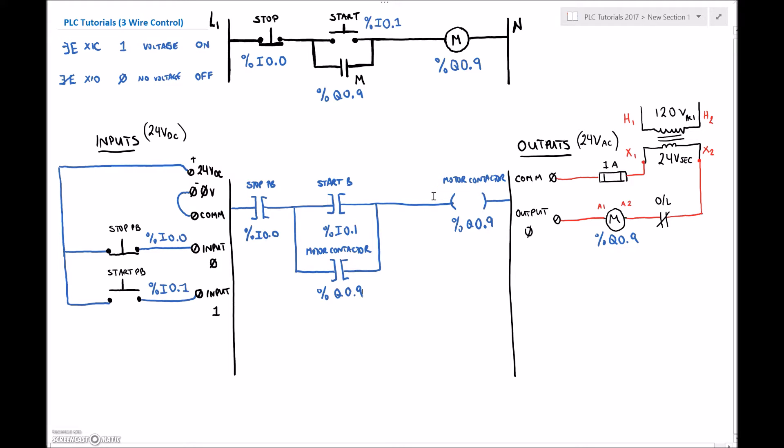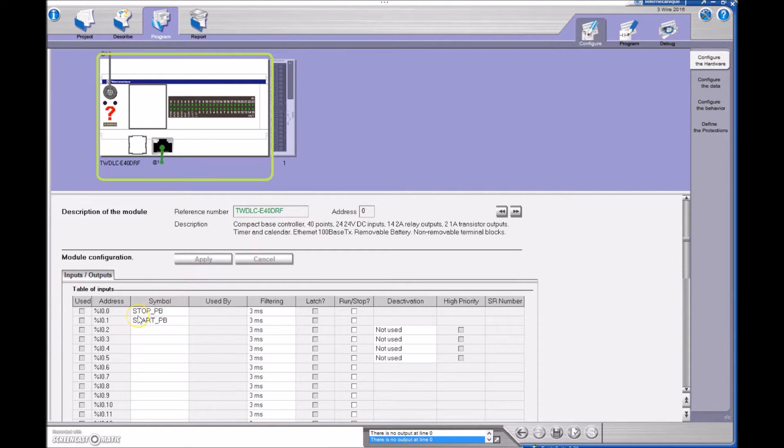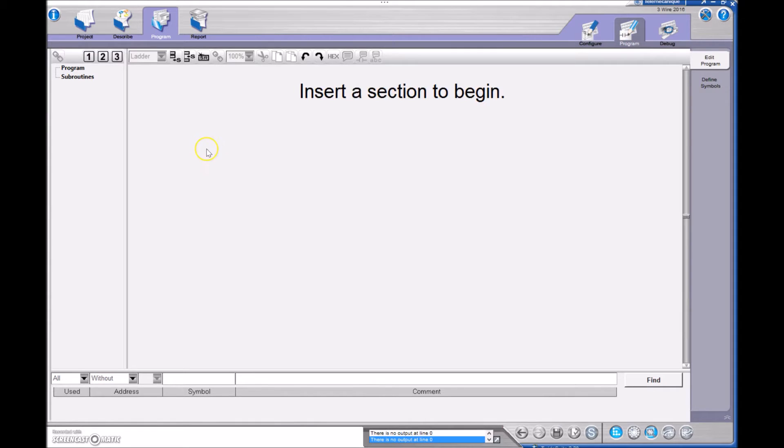We'll do the open loop for the three-wire, so let's bring up our Twido Suite. The first thing we're going to do is go to Configure. I've got my stop push button wired to input zero, my start push button wired to input terminal number one. Those are my two inputs. I only have a single output, and my output number nine is physically wired to my motor contactor, so I'm going to label Q09 as my motor contactor.